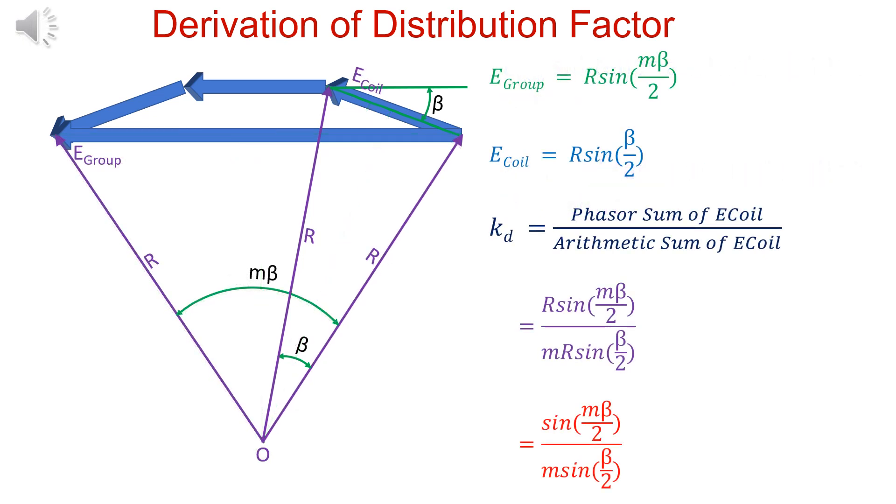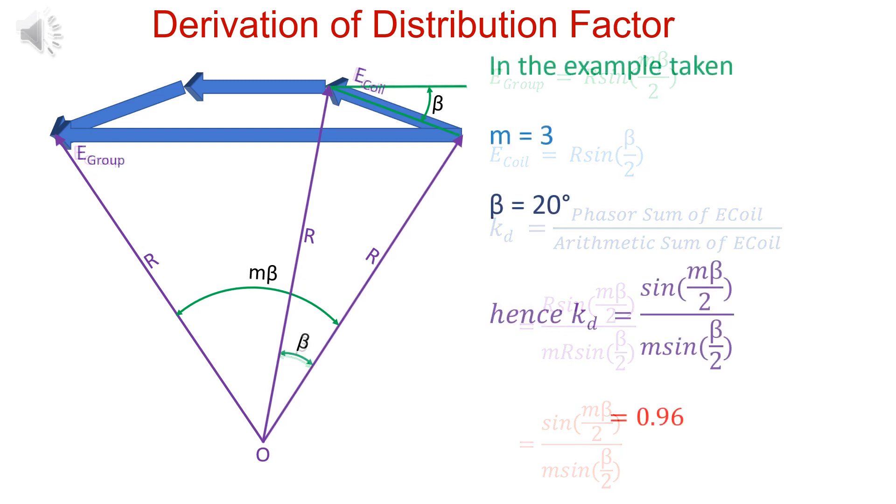As seen, distribution factor KD is equal to sin M beta by 2 divided by M sin beta by 2. In the example taken, number of coils in a group are 3 and beta equals to 20 degrees. Substituting these values, we get KD equals to 0.96.